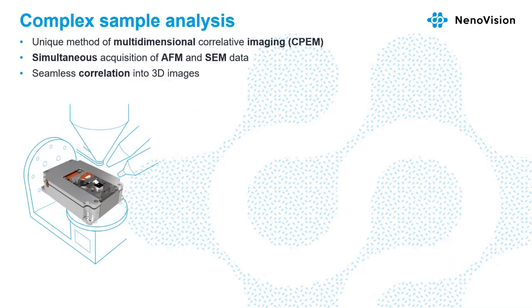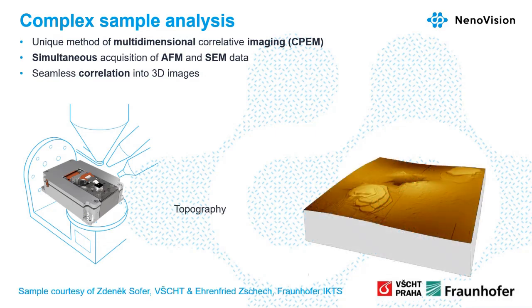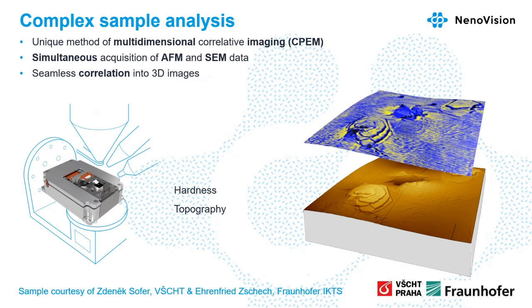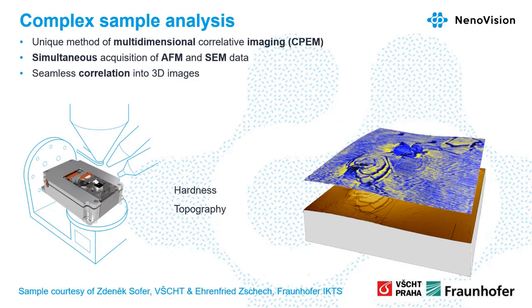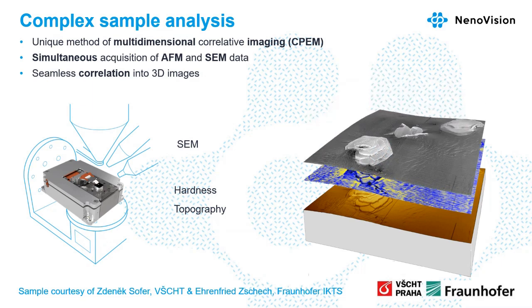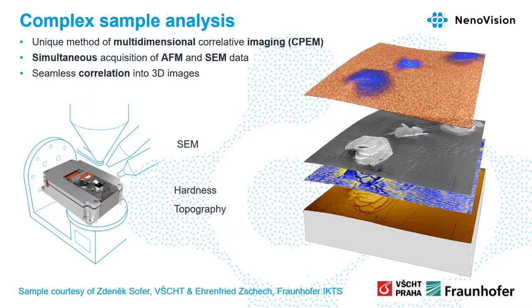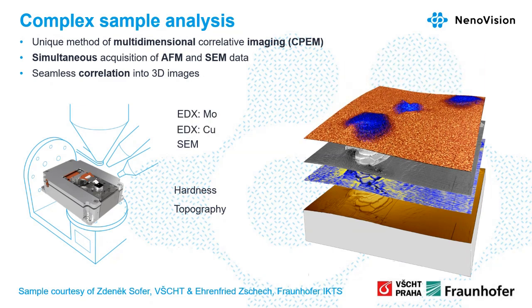The second was the complex sample analysis. It is a unique method of multidimensional correlative imaging, CPEM. I will be talking later about it. It can simultaneously acquire AFM and SEM data in seamless correlation into three-dimensional images. So if we have the topography, at the same time we measure the hardness of the sample with the material contrast from secondary electrons and with the EDS map. So as we see, we have from the same place more channels together correlated.